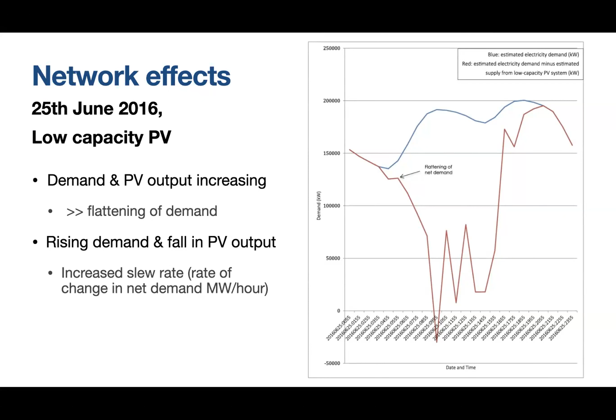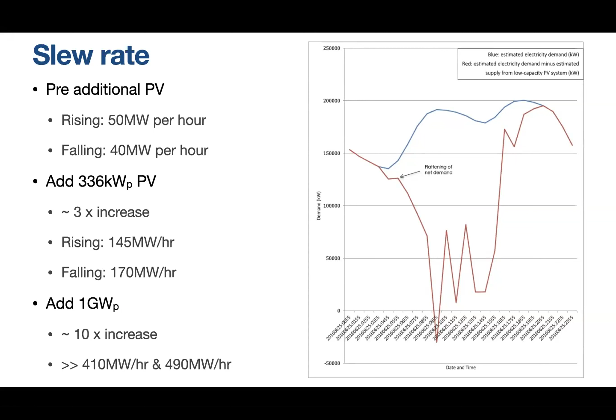That's one of the potentially significant outputs from this. Before adding PV, the rising slew rate was probably around 50 megawatts greater at its highest rate. As we start to add PV, that slope becomes steeper. Even with the low system it rose to about 145 when rising and 170 when falling, and it goes up roughly ten times if we're looking at a really big PV array, the 1 gigawatt peak system.